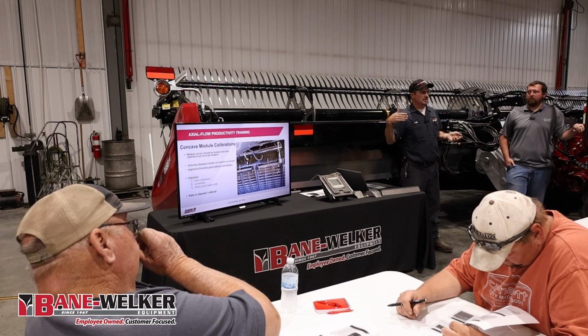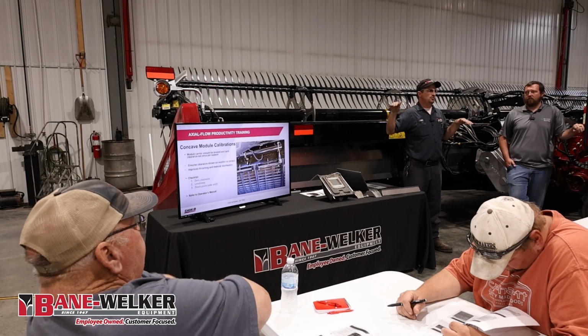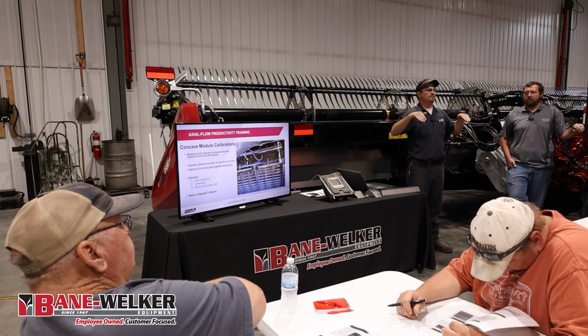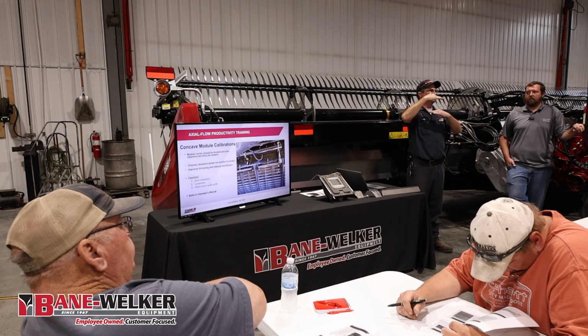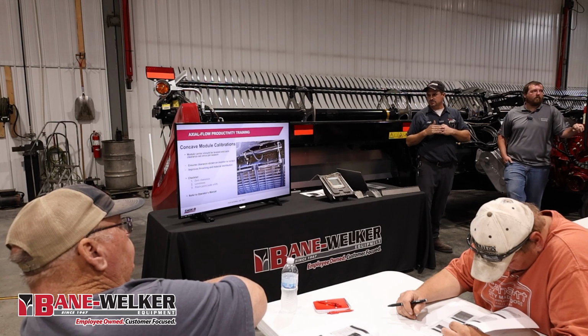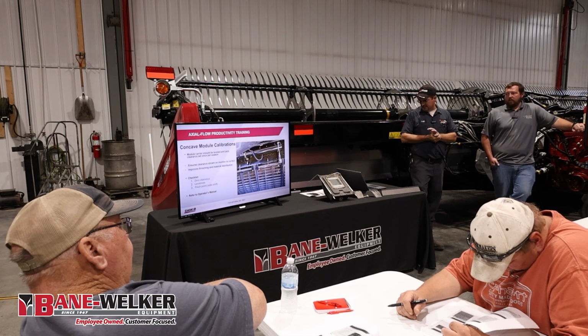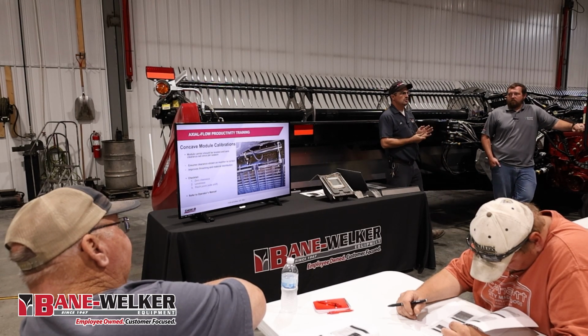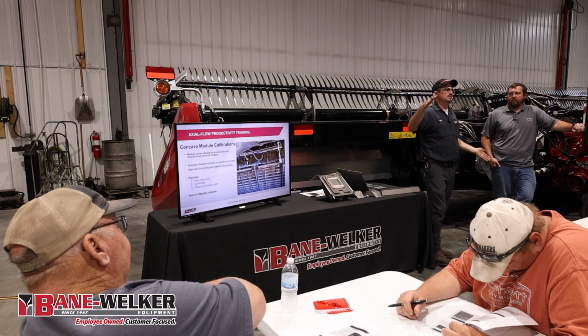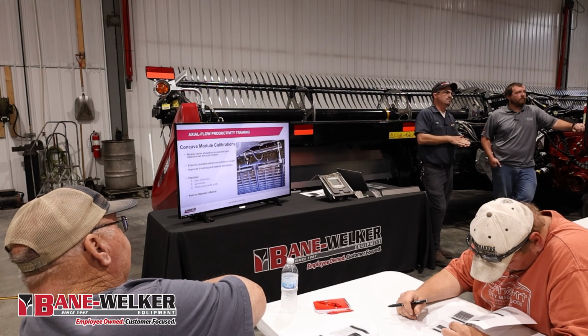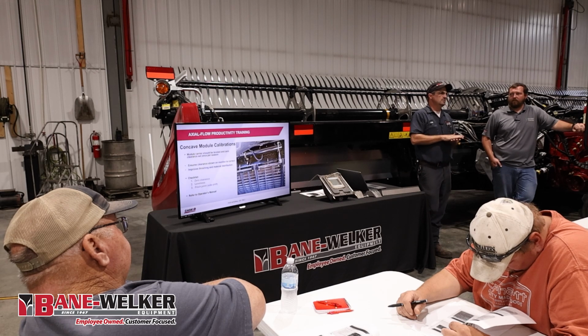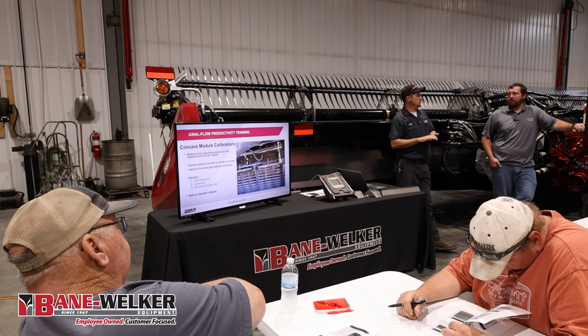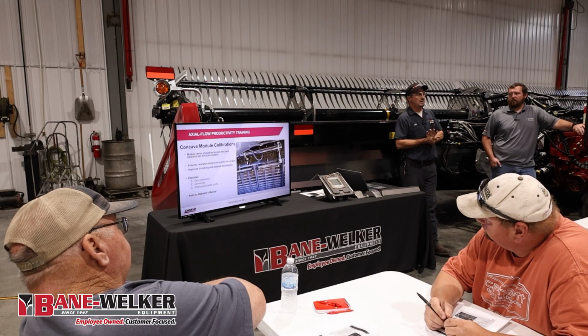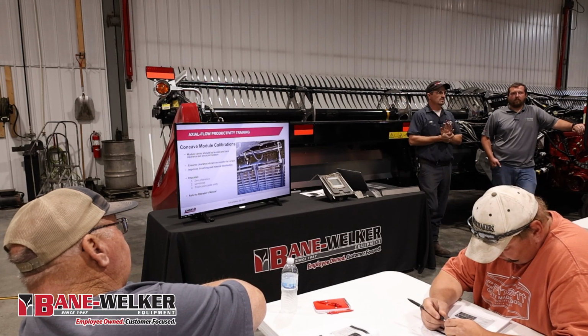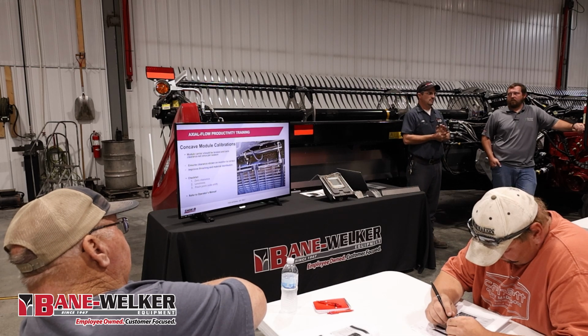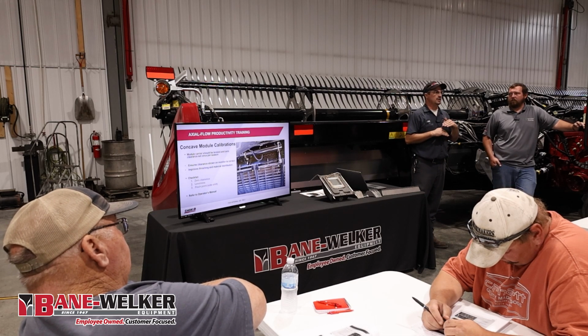If you have any of this apart, something gets bent, damaged, or wears funny, it's critical. Most of the time you can just take a measurement on the side of that frame, see where the lower frame sets to the upper frame, okay? That should be nice and straight. In this other picture, we also see the bolts. Those are our zero set point. That's the positive stop when this frame closes all the way up. It's critical. For one, that sets where your zero point is, so you can come back and calibrate where zero is later, okay? So that number, how many millimeters open that concave is for your automation, is critical.